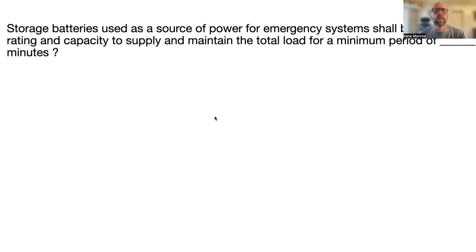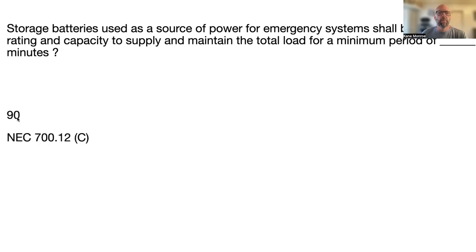Next question: storage batteries used as a source of power for emergency systems shall be of suitable rating and capacity to supply and maintain the total load for a minimum period of blank minutes. The answer is 90 minutes — you need 90 minutes for people to get out of a building. That's found at NEC 700.12(C). Highlight 700.12(C), 90 minutes.